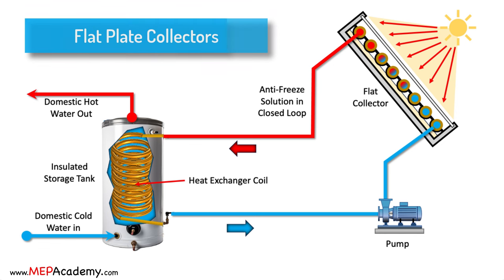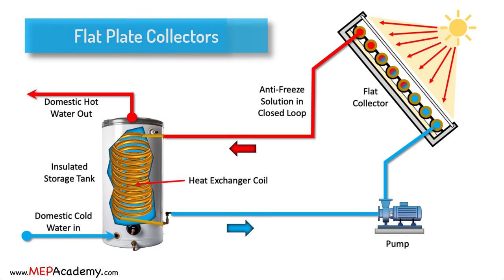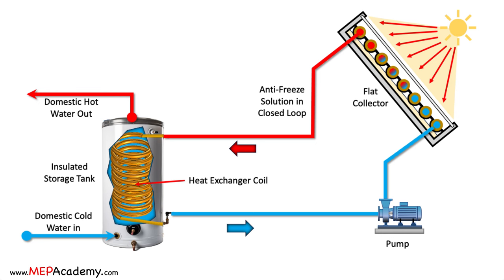Flat plate collectors are the most common type and consist of a flat insulated box with a transparent cover, usually glass on top. Inside the box is a dark absorber plate, typically made of metal or other materials with high thermal conductivity. Sunlight passes through the transparent cover and strikes the absorber plate, which absorbs the solar energy and converts it into heat. The heat is then transferred to a fluid, usually water or a heat transfer fluid, flowing through tubes attached to the absorber plate. Flat plate collectors are versatile and used in both residential and commercial solar water heating systems, suitable for moderate climates and domestic hot water applications.